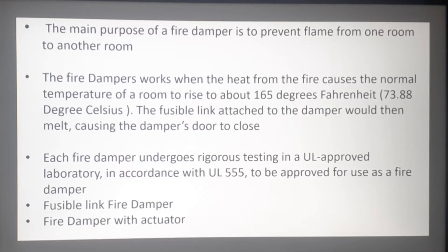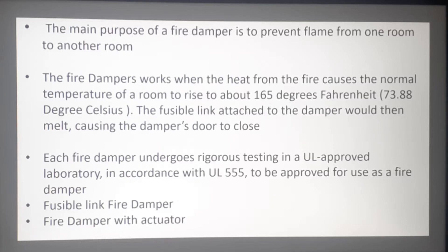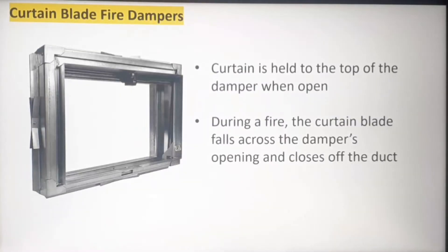In a fusible link fire damper, there is a fusible link that melts at a certain temperature. For example, if room temperature is around 28 to 30 degrees Celsius and it rises up to 73.88 degrees Celsius due to fire, the link will melt and the damper door will close. Once the damper door closes, air cannot travel from one end to the other.